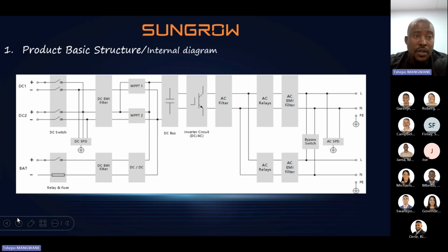Okay, now we're going to look at the product basic structure, the internal diagram. This is the internal diagram of the basic 6 kilowatt inverter or 10 kilowatt single phase. It's not the 3-phase. Okay, there's our MPPT1, MPPT2. As I've mentioned, per string it's 600 volt max. The startup voltage on it is 40 volt. This is our common isolator switch. And not to forget to mention that we do have DC surge protection on this machine, type 1 and 2, which is surge and lightning.